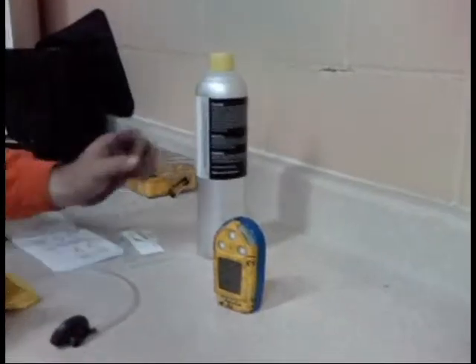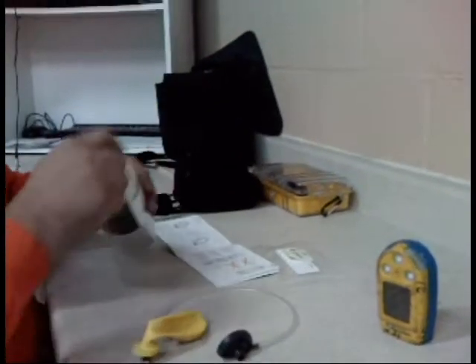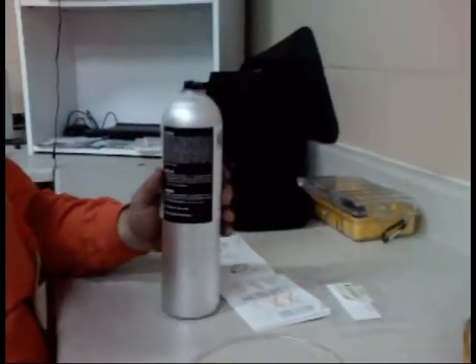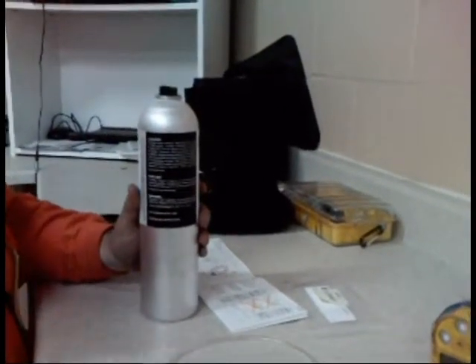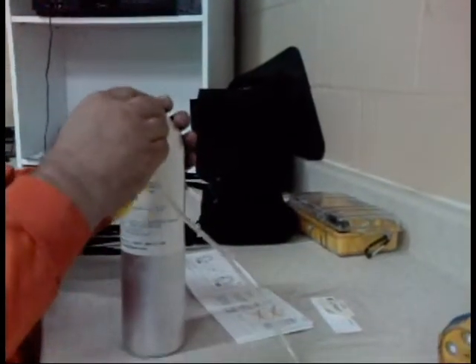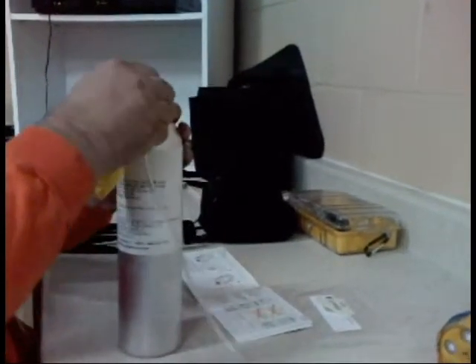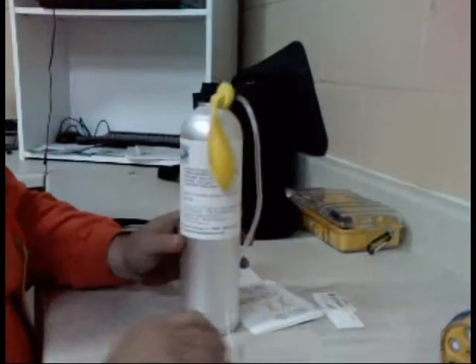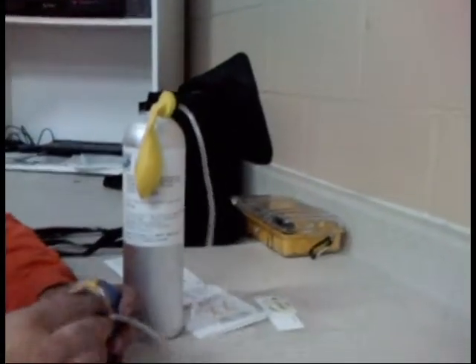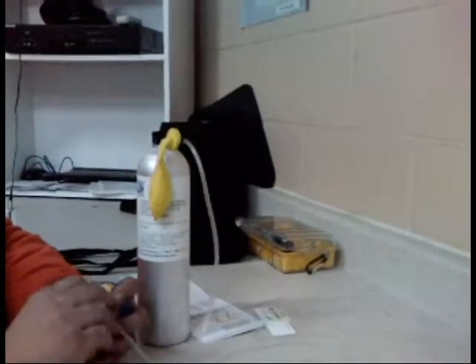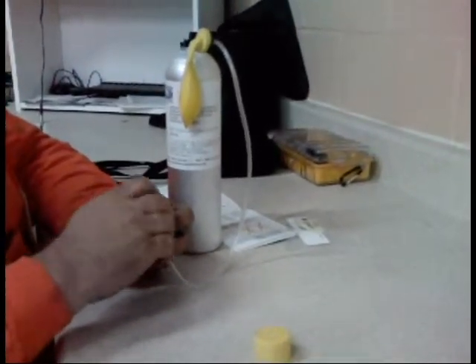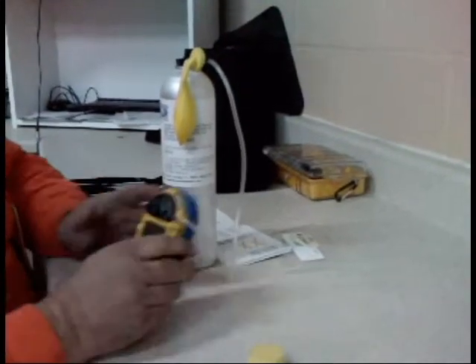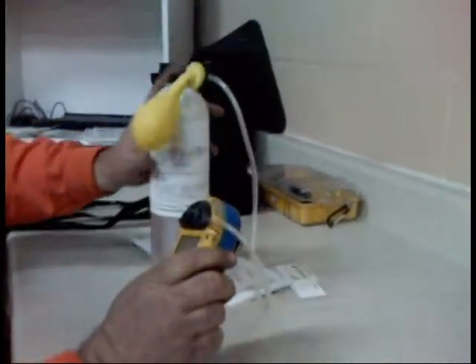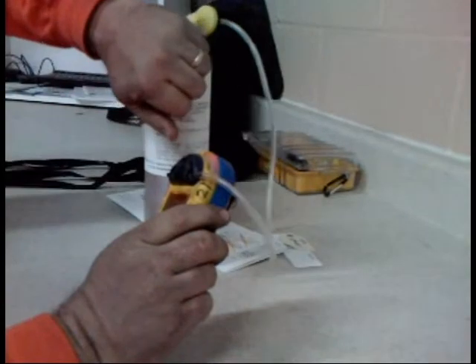There you go. Okay, now we'd like to show you a simple bump test. This is pretty easy. It's just showing you that the sensors are working and the alarms are working. First thing we'll do is we'll take our spray bottle, which is a lot like our calibration gas, but instead of a regulator, it's just got a simple button. We'll hook the adapter onto the unit. Just a little push, fill up the balloon.